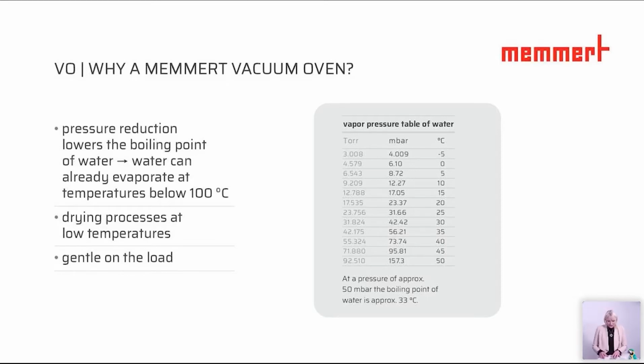That's what we see here on the vapor pressure table. On this table you'll see on the middle line the millibars mentioned, and also the Celsius degrees. As lower as we go in pressure, as lower is the boiling temperature. Here we have at a pressure of approximately 50 millibar, a boiling point of water of approximately 33 degrees. That is really, really low.